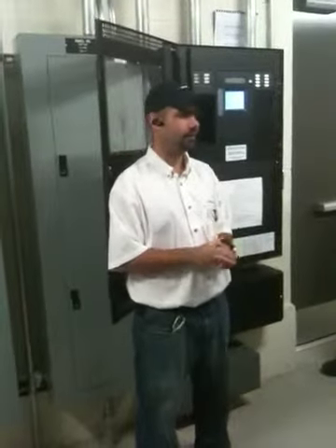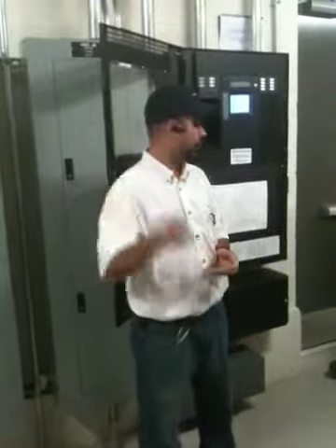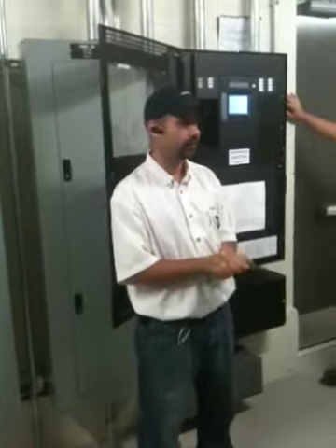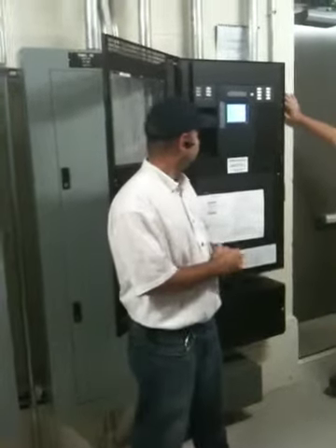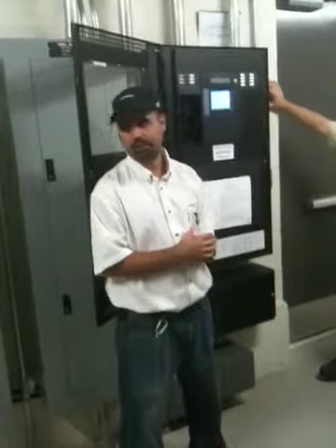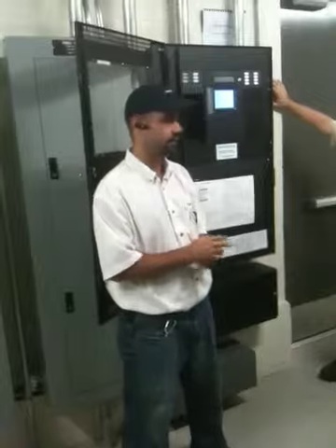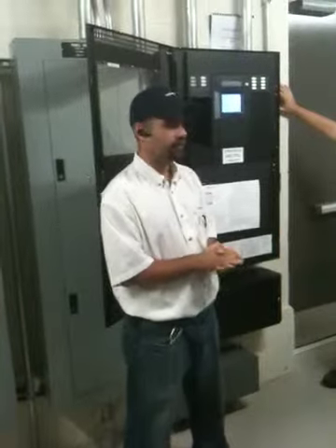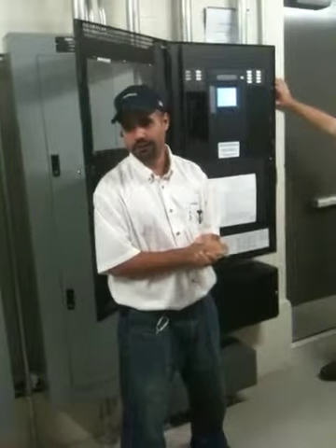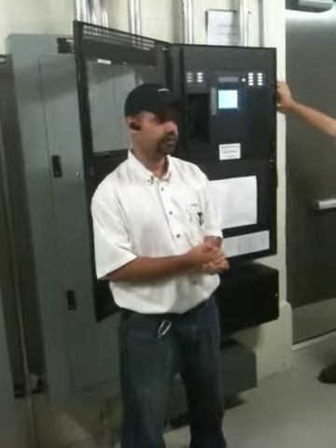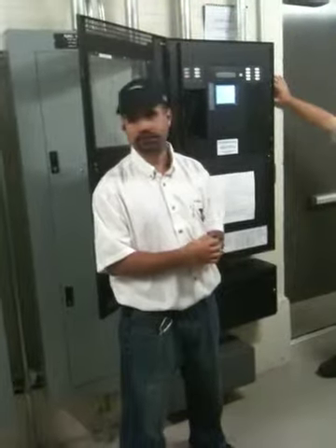We have elevator recall for both elevators that goes all the way up to the fifth floor. We have shunt trips for the elevators, primary, alternate. Then in all of our mechanical rooms, electrical rooms, and certain areas we have smoke detection. We have pull stations, and we have 2 air handler units, which we are shutting down as well. Each unit has a supply and a return duct detector. Those units also have remote test switches and remote LED indicating lights to show the status of the actual detector, if it's active or not.